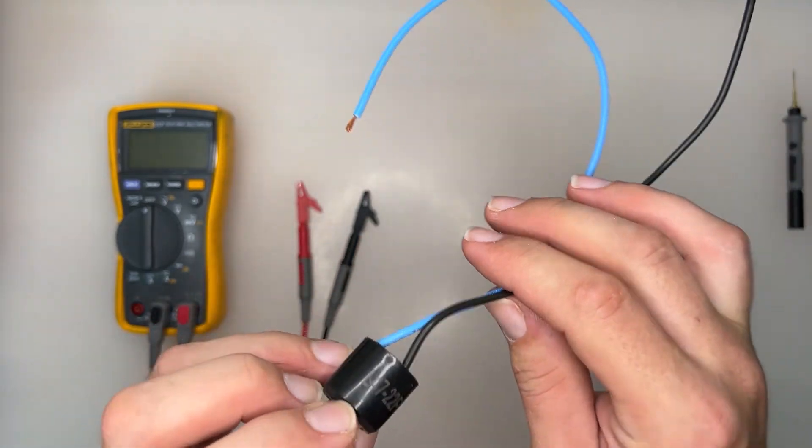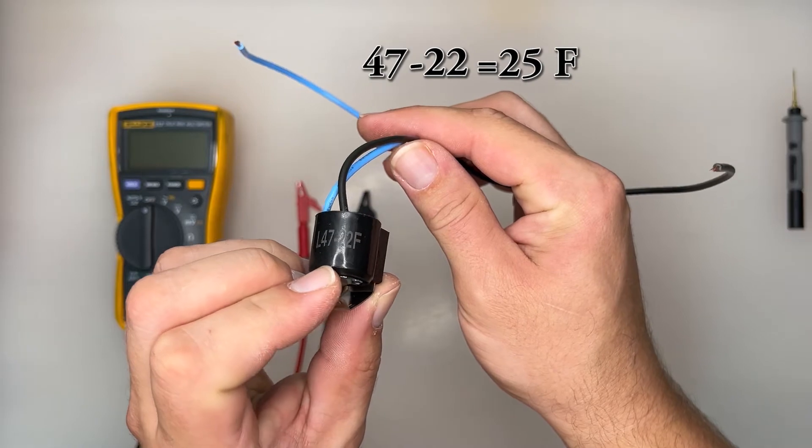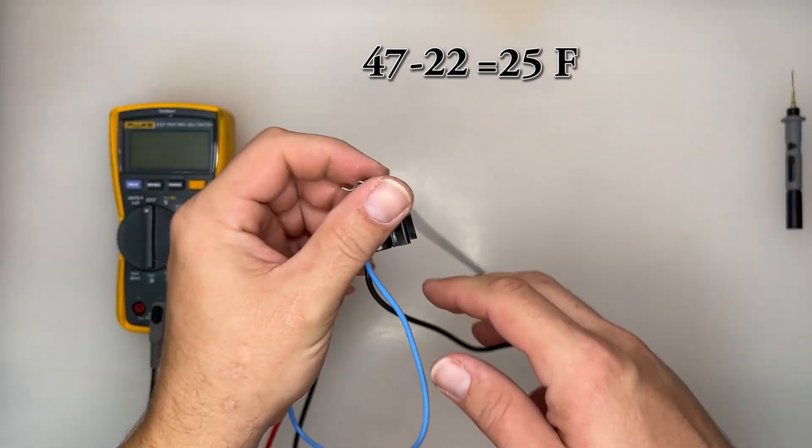Follow closely. Limit temperature of 47 is when the thermostat opens. Minus 22 equals 25 Fahrenheit. That is when the thermostat closes.